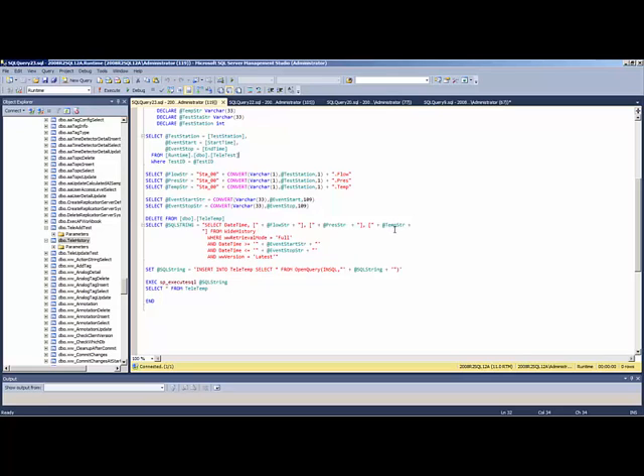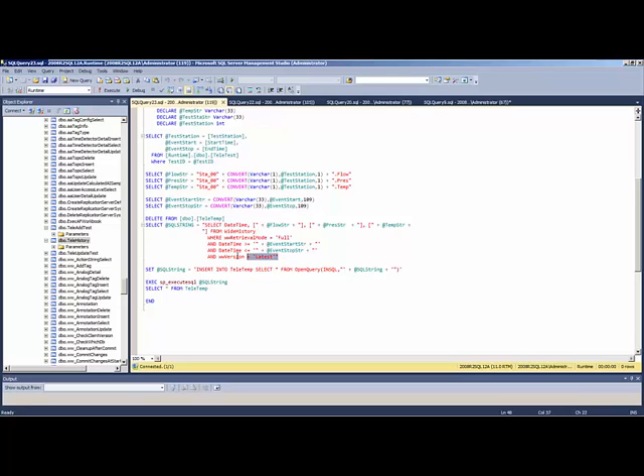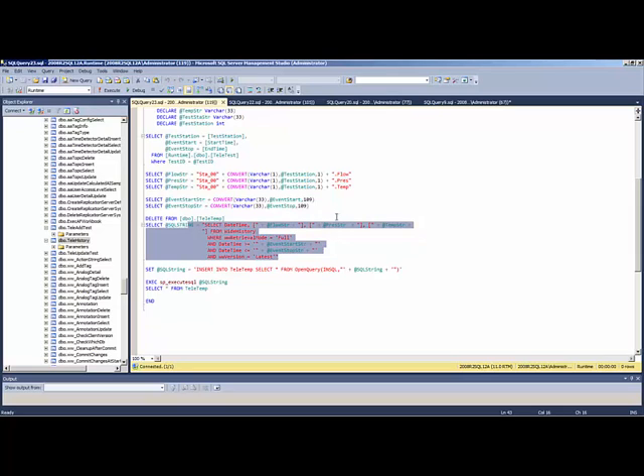Here's the actual query we're going to execute. We're passing in those tags from the Wonderware Historian, using something called the wide history table, and passing in the start and end time to extract the information. We build that into a string and then use the OpenQuery function within SQL to execute that query — passing parameters in, extracting information from the test table — so we can correlate the actual process data: the flows, temperatures, and pressures from the actual test event that happened.